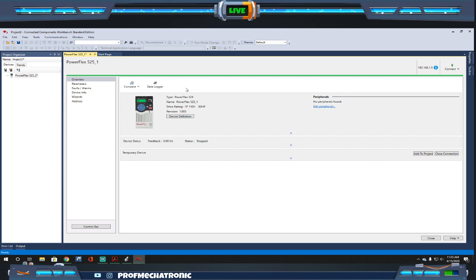One piece of information I think is pretty important: once you set the IP address on your drive, you have to cycle power. Cycling power allows the drive, on boot, to actually use that new IP address. So if you input your IP address on the drive and for whatever reason it doesn't seem to take, or you can't communicate, just do a quick power cycle to make sure the parameters got saved and are active when the drive boots up.